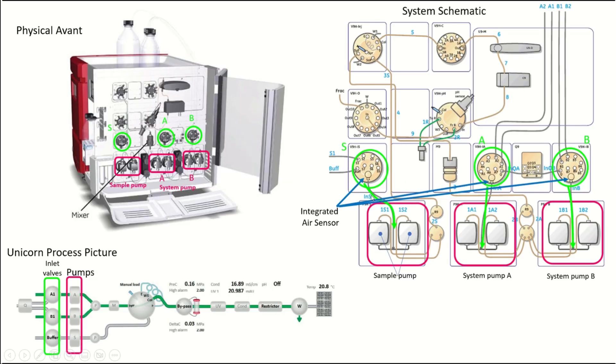Each of the inlet valves has an integrated air sensor, and this is really helpful. You should have these on for most of your chromatography runs. The A and B air sensor is really helpful for protecting the column. The S air sensor is helpful for telling the system when your sample is being loaded if that's how you're loading your sample using the sample pump.